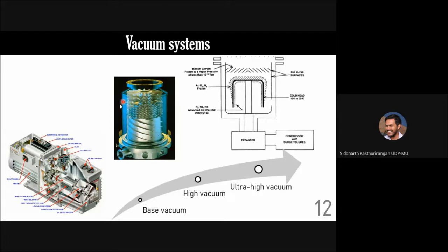These blades are rotating at extremely high rotation speeds, typically 500, 600 hertz, sometimes even 1000 hertz. Very, very fast rotation speeds. Molecule comes randomly, gets hit, goes down, and gets sucked out from here. That's the basic concept of this kind of pump.